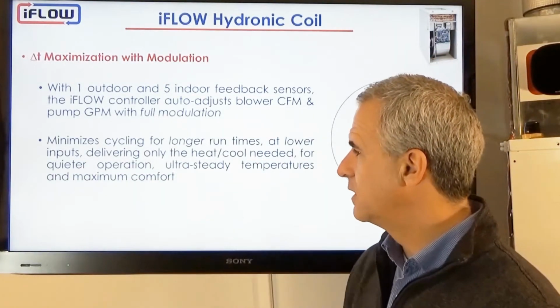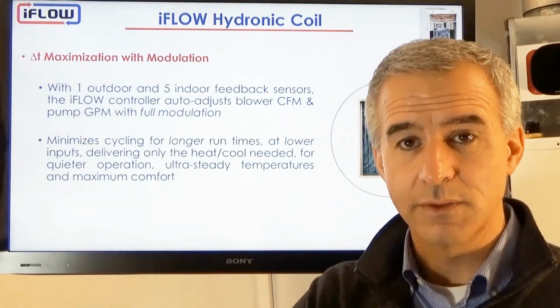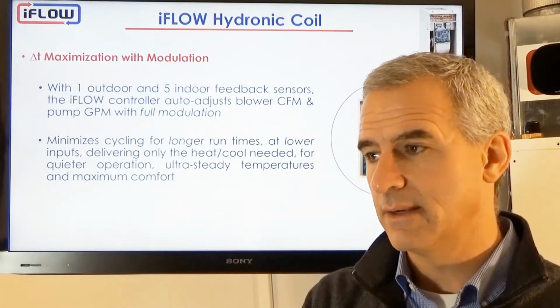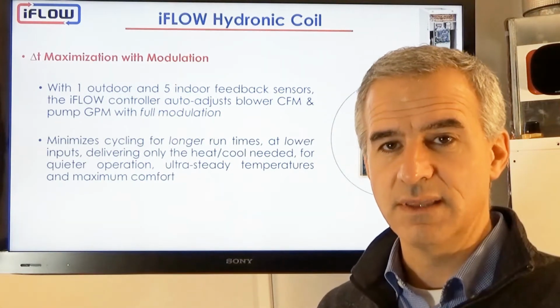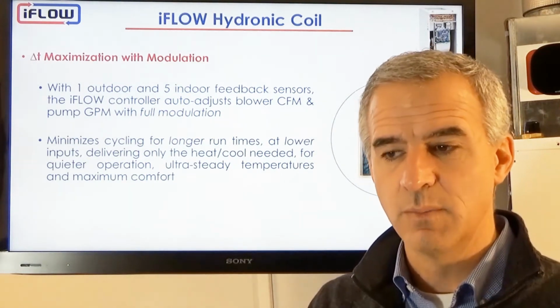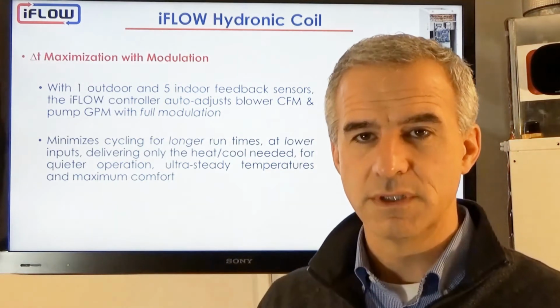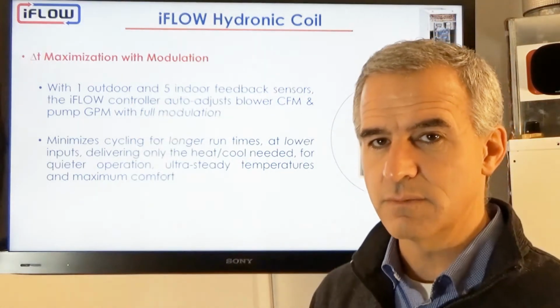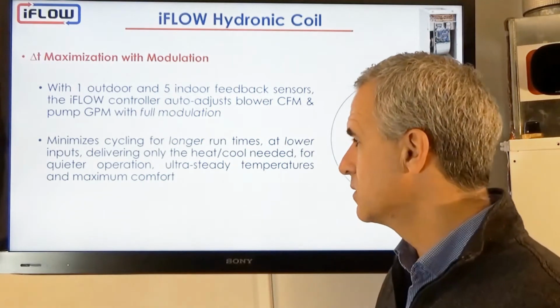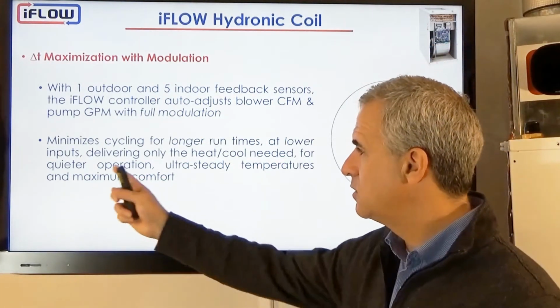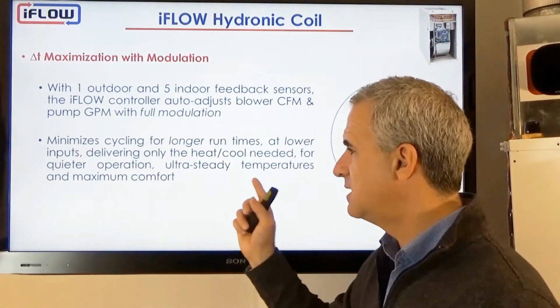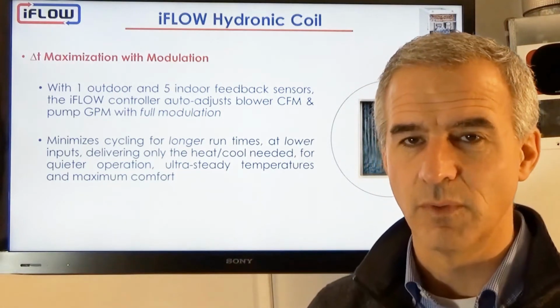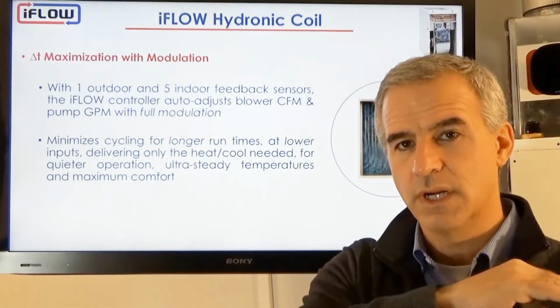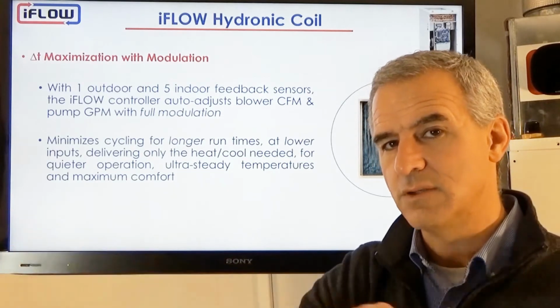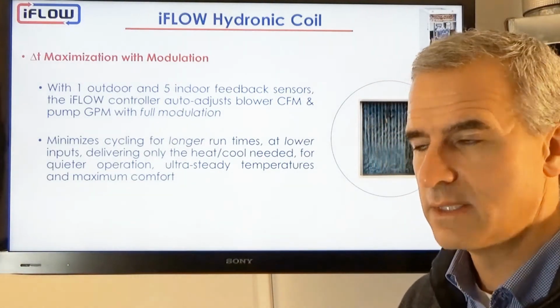Delivering only the heat and cool that's needed makes for quieter operation, because we can modulate down. Instead of running at a CFM required for 60,000 BTUs, we can run at a CFM equivalent to the BTUs required. If that's 35,000 BTUs, then we can run at that CFM level. So running at lower BTUs gives quieter operation, ultra steady temperatures, and that's maximum comfort. When we're not cycling off and on and we're just running continuously at the BTUs required in the space, it's excellent comfort.